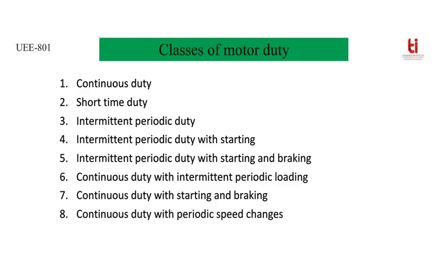Then intermittent periodic duty with starting and braking. During starting conditions, whatever temperature rise is there, and then during braking conditions, the change in temperature, we have to consider. Based on that, we have to design the motor or select the motor rating. That's why these classes are important. Then continuous duty with intermittent periodic loading. That means the machine is continuously on for some duration of time and some load is there. In the next duration of time, the load is removed, but the machine is not off.